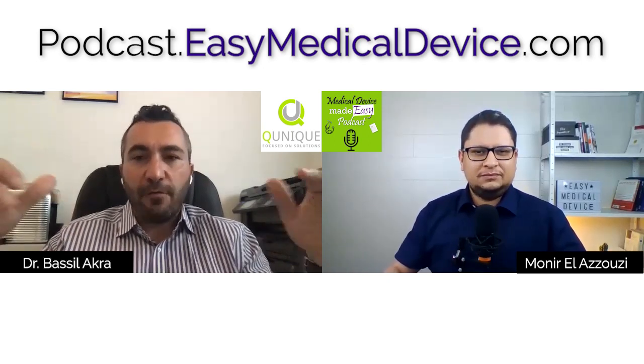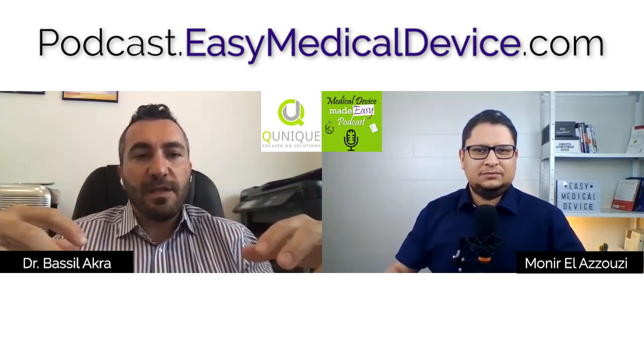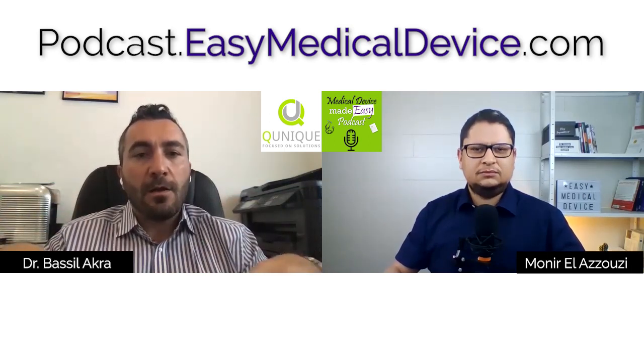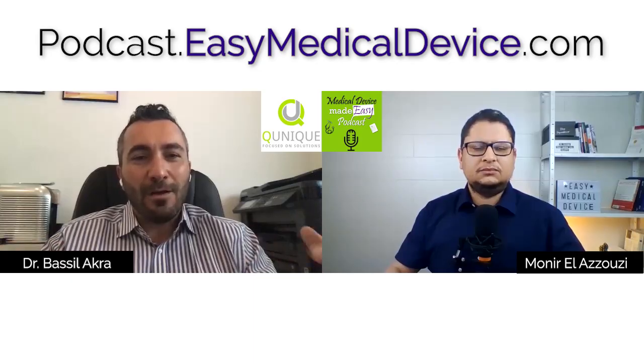Yeah, so let me explain first of all the legal requirement in Europe. The first thing is a requirement comes from the regulation. Guidance documents are just helpful documents which are guiding you towards the fulfillment of the requirement. So the highest level of expectation always comes from the legislation, not from the guidance document. If there is any differentiation between guidance and regulation, always the regulation will be the one which is applicable. Everything else is invalid if it is written in a way that contradicts the regulation. So the regulation has the main power to implement rules in Europe, and the guidance are just instruments to help you in that direction.